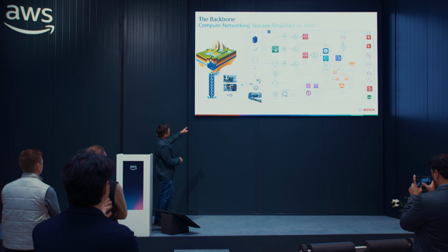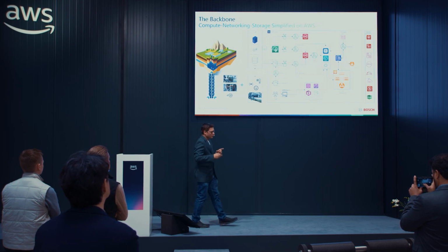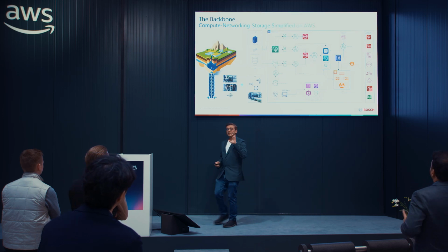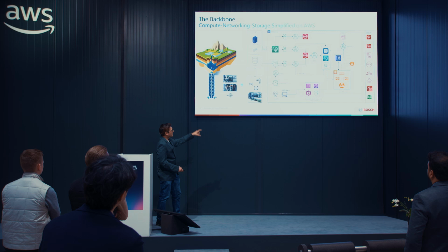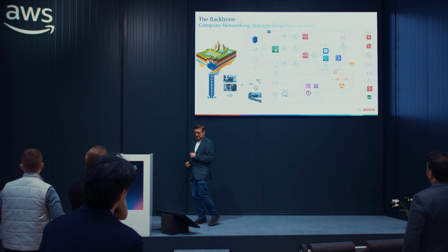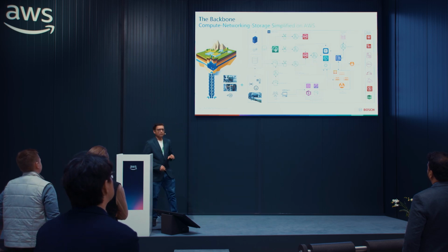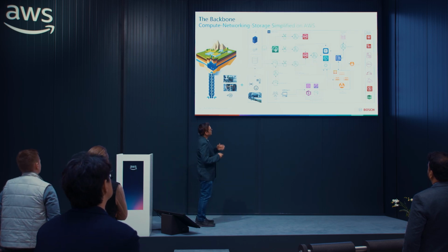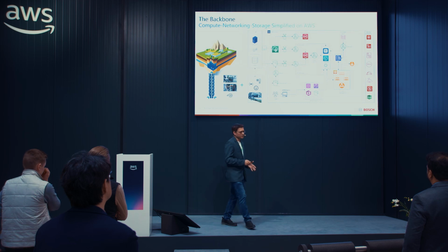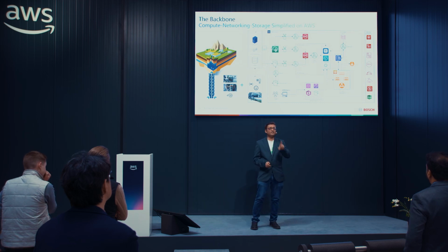Here you see the pump is being connected to the MCSA, and then the IT/OT integration happens. So the IoT Core of AWS is so sophisticated, it can take data up to 12 kilohertz. At the same time, you can easily integrate the IT/OT data. Then following this, the live streaming of the high frequency data can also be done using the Kinesis environment. And the best part was using the AWS environment, the Lambda functions, very specifically, and the ECS functions to run the physics-based models and the simulations, which is very difficult to run.